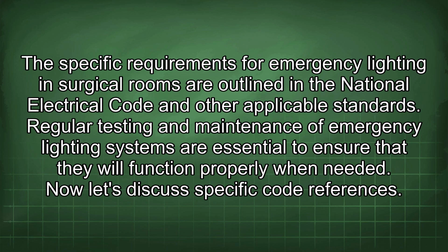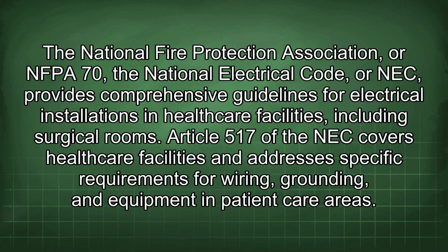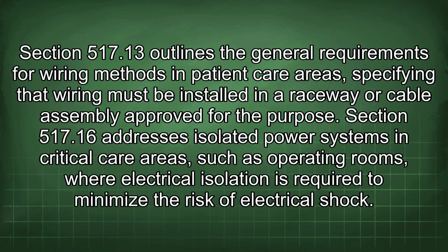Now let's discuss specific code references. The National Fire Protection Association's NFPA 70, the National Electrical Code, or NEC, provides comprehensive guidelines for electrical installations in healthcare facilities, including surgical rooms. Article 517 of the NEC covers healthcare facilities and addresses specific requirements for wiring, grounding, and equipment in patient care areas. Section 517.13 outlines the general requirements for wiring methods in patient care areas, specifying that wiring must be installed in a raceway or cable assembly approved for the purpose.